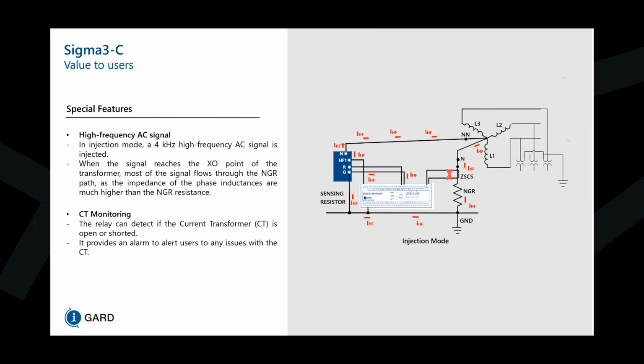So as mentioned, the high frequency injection mode is a 4 kilohertz signal. And when the signal reaches the XO point of the transformer, most of the signal flows through the NGR path, as the impedance of the phase inductances is much higher than the NGR resistance. And with the CT monitoring that we've also placed inside of this relay, we can detect if the current transformer is open or shorted, and it provides an alarm to alert users to any issues with the CT as well.